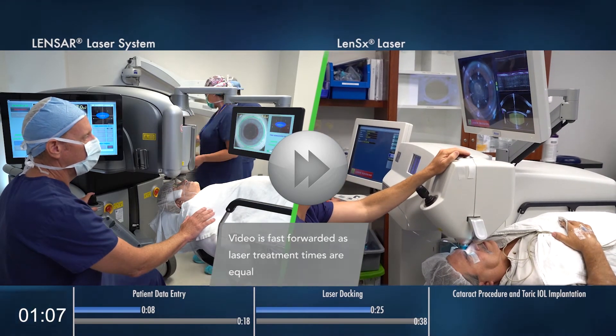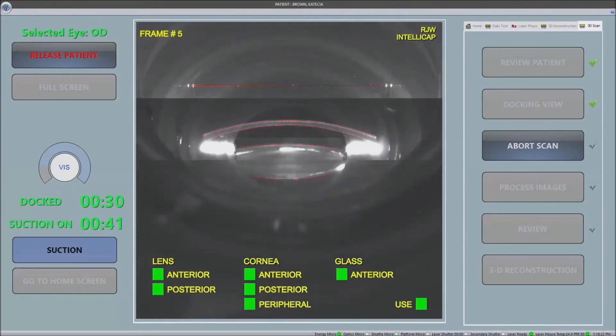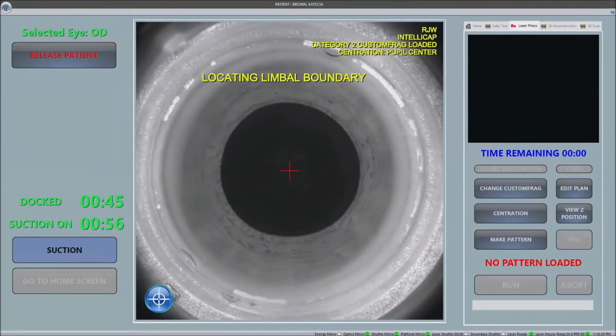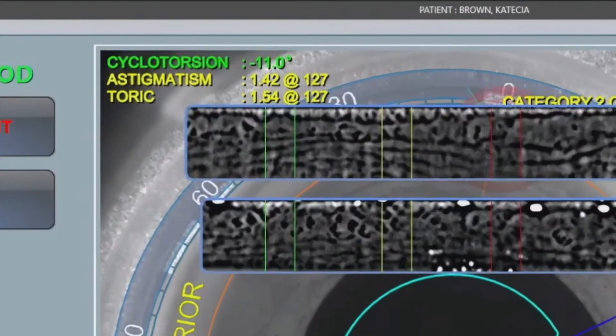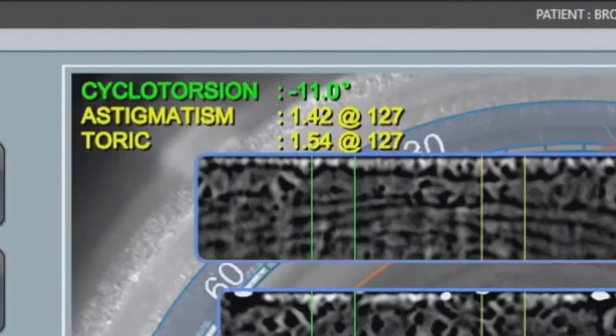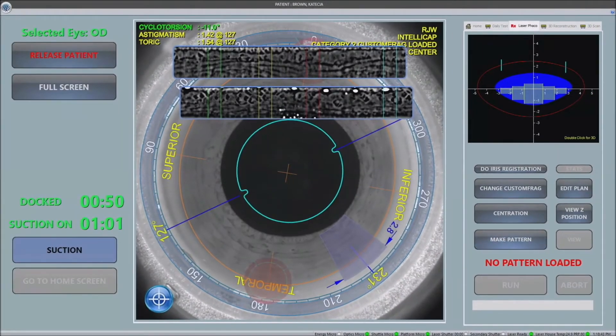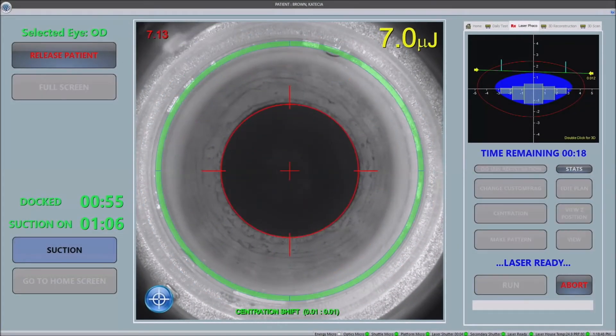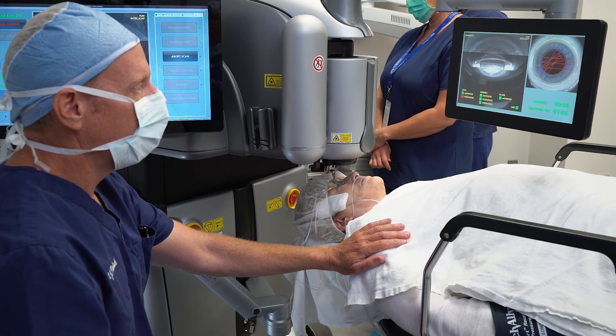In terms of addressing astigmatism, LENSAR gives us the broadest options available. Arcuate incisions can be used to fine-tune outcomes, or toric IOLs can be aligned with LENSAR's proprietary IntelliAxis refractive capsulorexis. Treatment of astigmatism is precise because of adaptive astigmatic guidance, which uses iris registration to automatically correct for cyclotorsion. When performing arcuate incisions, the LENSAR laser automatically adapts to the parameters based on the surgeon-preferred nomogram and surgically-induced astigmatism.